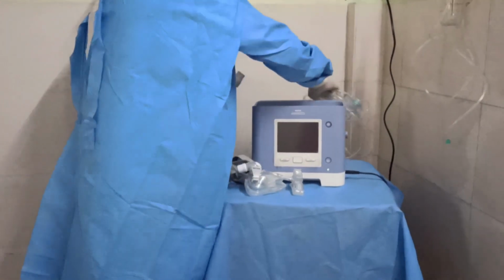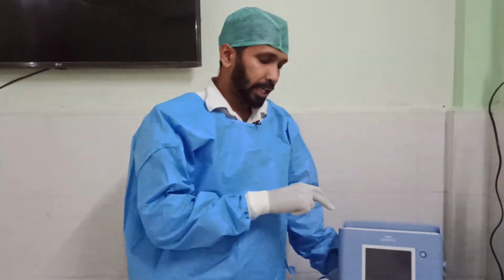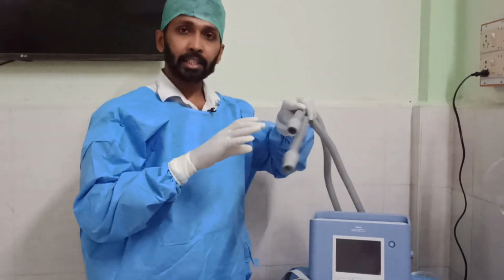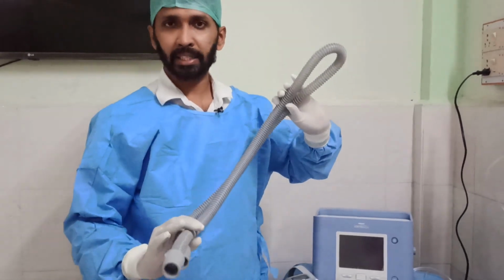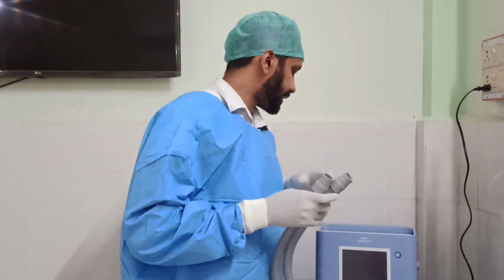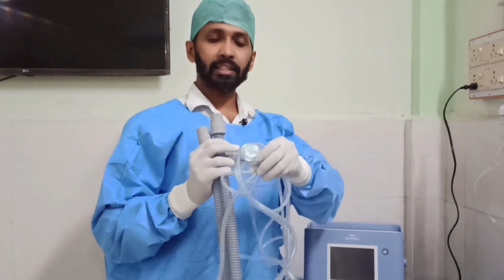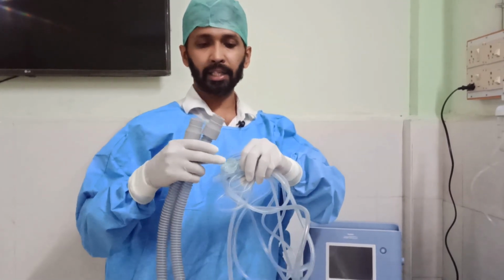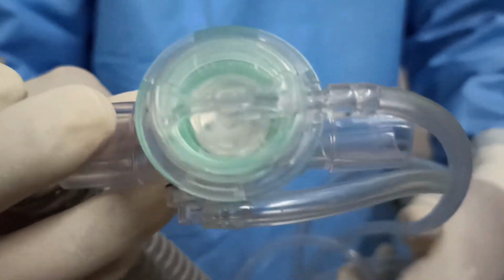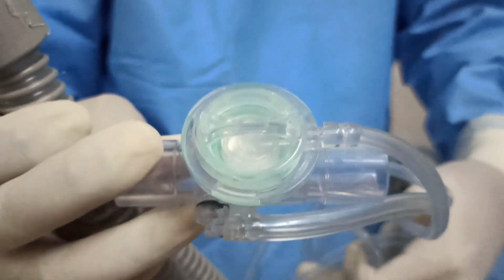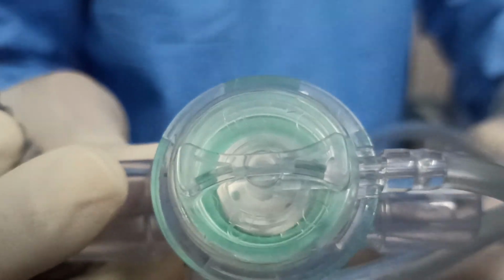Before starting, I will tell you a most important thing: this ventilator, as I already told, may be used for both invasive and non-invasive ventilation. So this is a single circuit ventilation. There is no separate tube for the expiratory cycle. So when you are using it for invasive ventilation, you have to connect this expiratory valve so that when the patient exhales, the air goes out through this valve. You can see this is the expiratory valve. This valve should be connected just before connecting the patient, so that the patient's expiratory air goes through this valve.